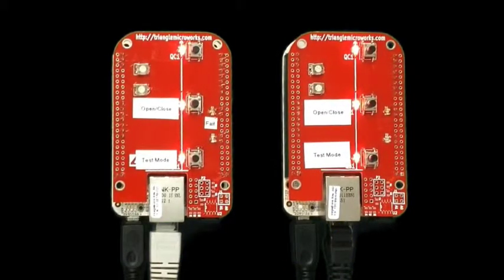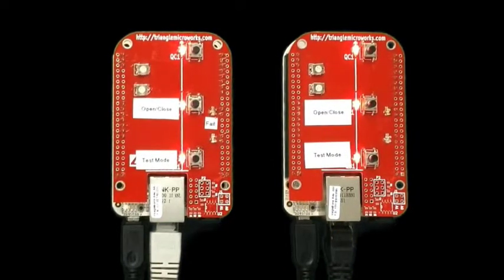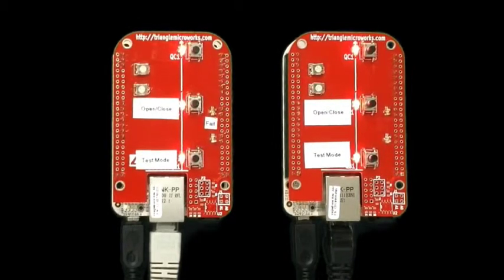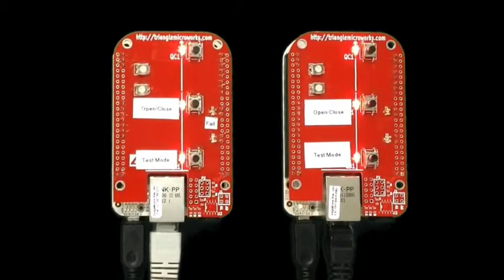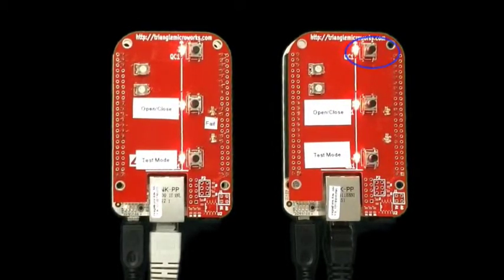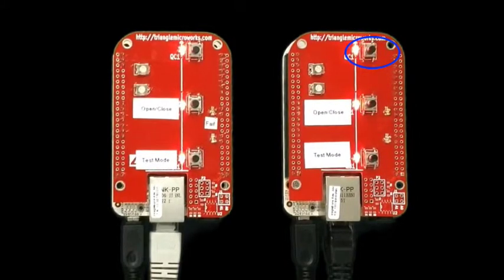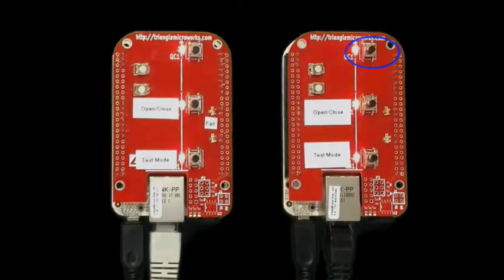The second board simulates the next breaker up the line. This board receives the goose messages, recognizes the downstream breaker has failed, and opens its breaker. The open condition is shown via the LED lights.